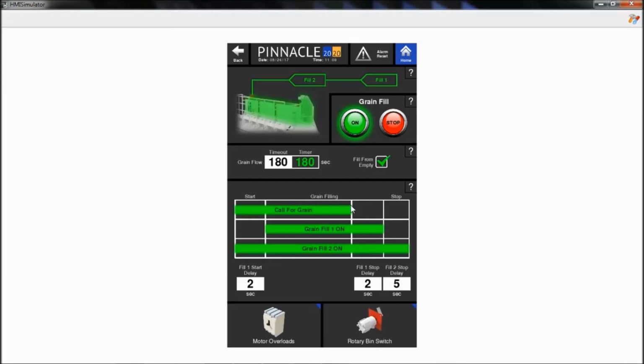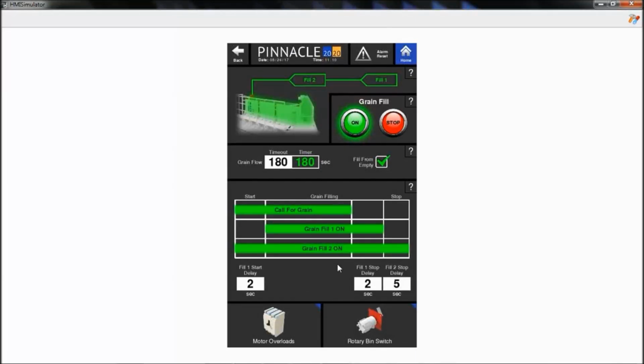In this case, for 2 seconds after you lose your call for grain, all of your equipment is going to continue to run, at which point the fill number 1 signal will turn off, and fill number 2 will continue to run for an additional 5 seconds. So we don't expect you to memorize how this toggles on and off, but you have charts here that help indicate what happens during each stage, and we have some descriptions here about what exactly each of these input fields does for each of these timers.